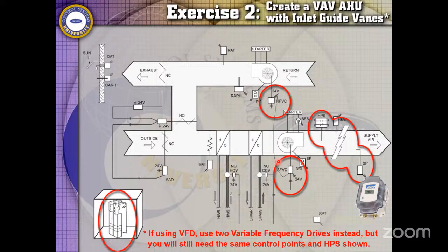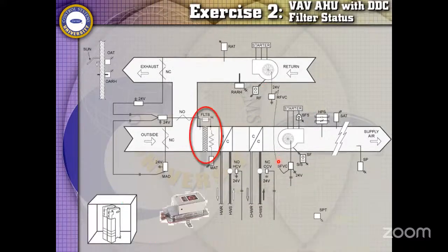I started doing controls in '97. I never put a high pressure switch on the VFD. My original boss wanted us to do it, and I was like, why? What is it going to do? I already got this other pressure sensor. Why do I need two pressure sensors? Well, this one's hardwired in case all the controls take a dump. Like, you mean the controls that we're programming? They're not going to take a dump. We're programming them. We're smarter than an average idiot. We weren't, but in this case, we were.